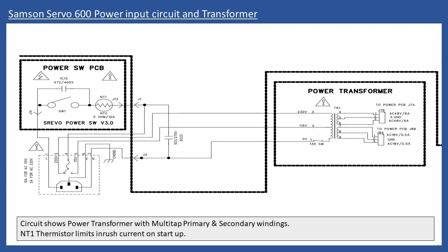Now when you have a multi-tap transformer, you may also have transformers which we call dual primary, and what that means is that you have 2 windings on the primary of the transformer. In the case of say 230 volts, you may have one of the windings which is 0 and 115 volts, and then the other one is 0 and 115 volts. And you think, well, what's that about?